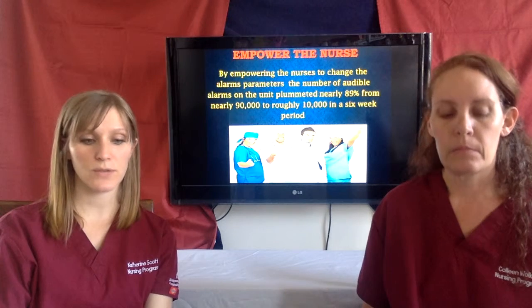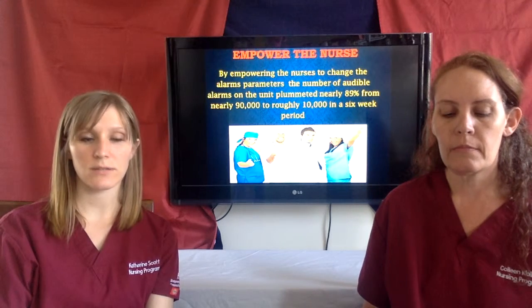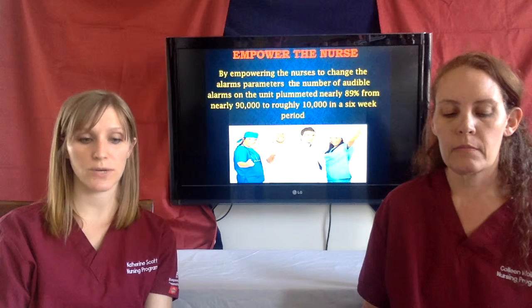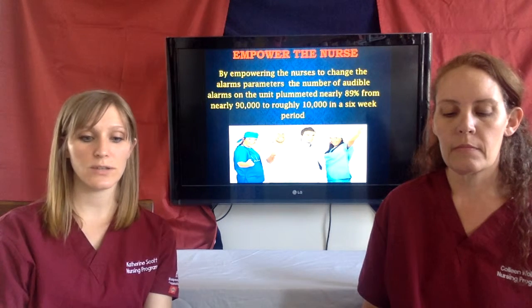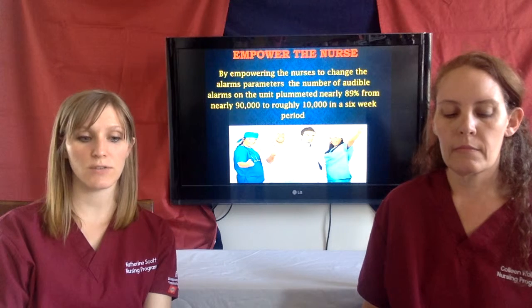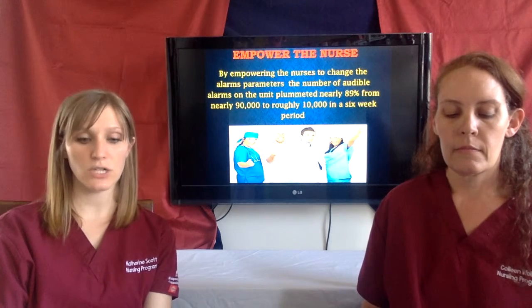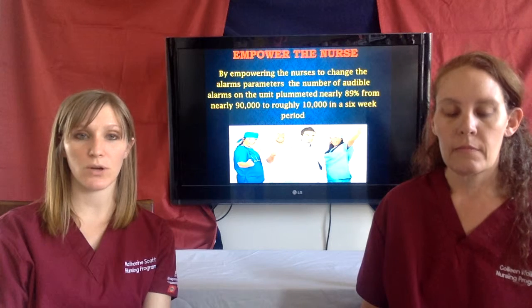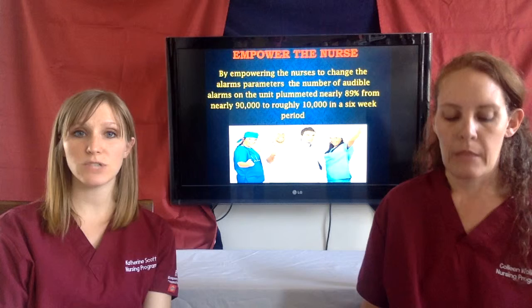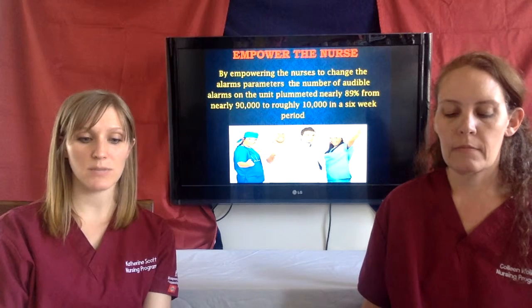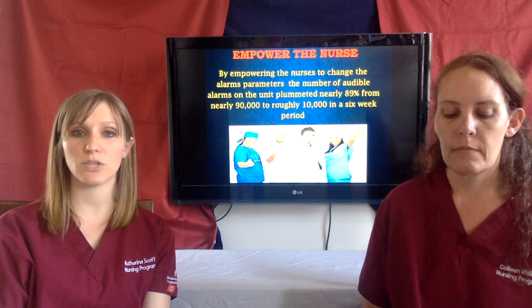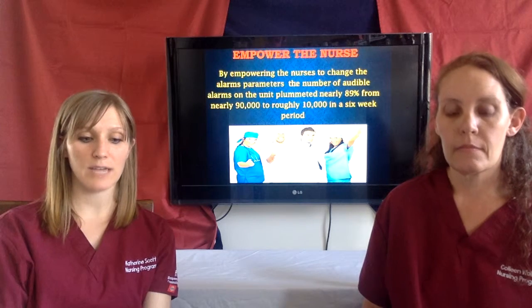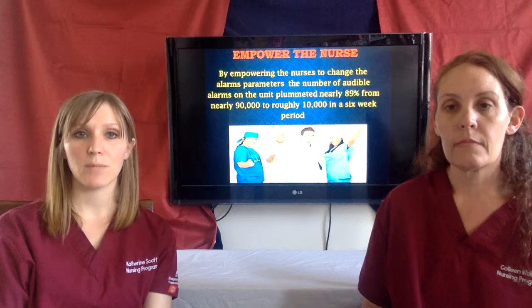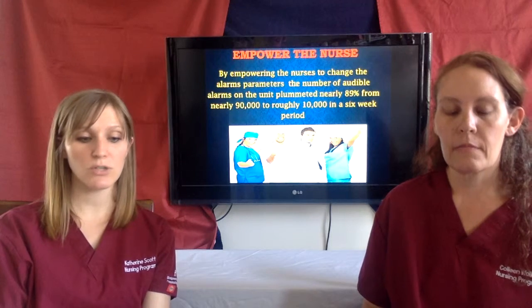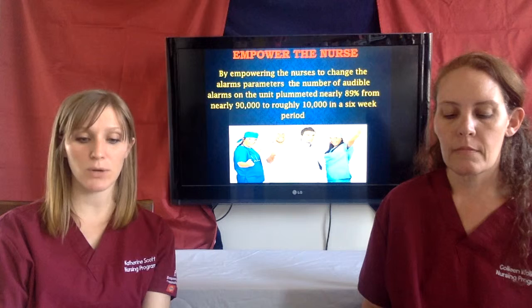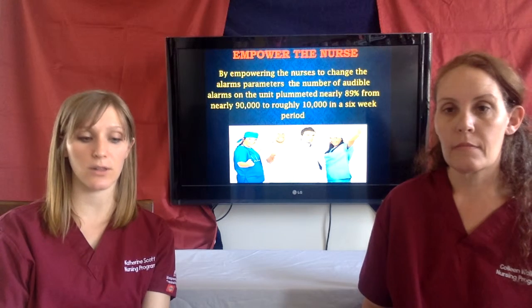In April 2013, the Joint Commission, the nation's largest hospital accreditation organization, issued a Sentinel Event Alert warning of the dangers of alarm desensitization and urging hospitals to beef up alarm management protocols and alarm settings. As of January, hospitals are required to demonstrate that they have made alarms an organization priority and identify the types of alarms that they plan to target. By 2016, hospitals will have to develop and implement specific protocols aimed at curbing unnecessary alarms.